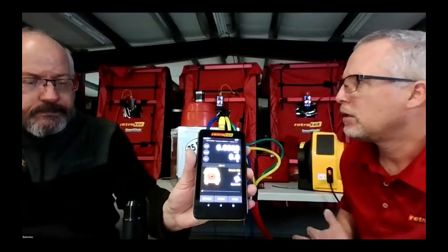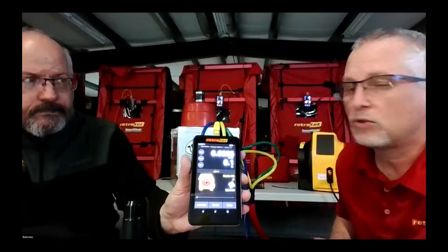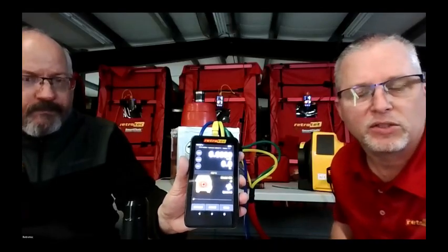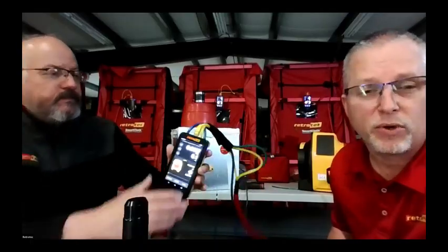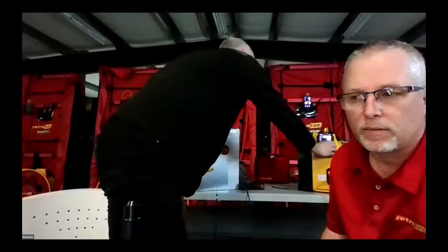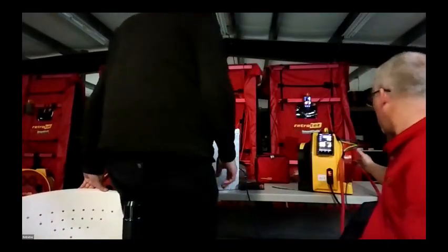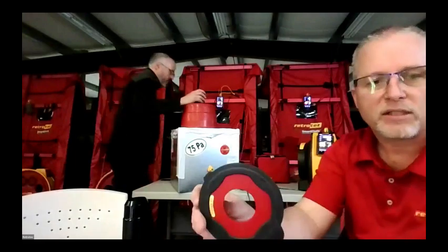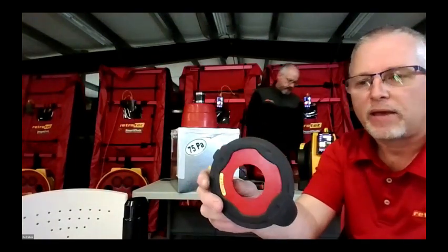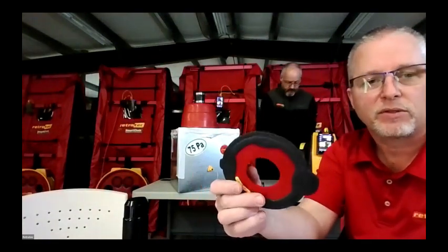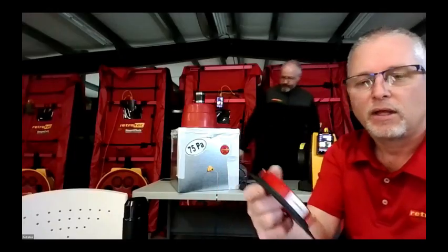It can measure down to 0.29 CFM with some additional orifice plates. With the stuff that comes stock with it, I believe it's down to about 2.9 CFM, so just under 3 CFM. The orifice plates are very easy to change out. They just snap in and snap out, and it comes with 5 different ones to get you there.